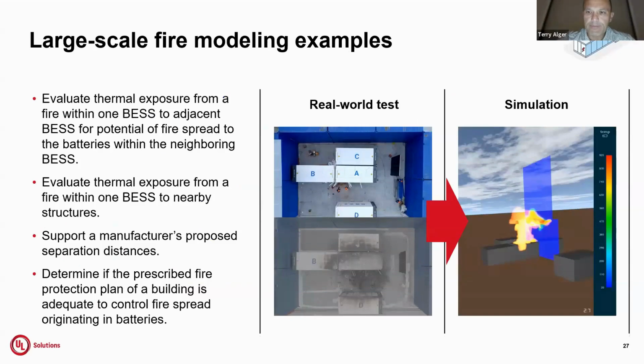Finally, there's a requirement to evaluate the thermal exposure from a fire within one BESS to adjacent BESS. This is key because in many of the significantly dangerous accidents that have occurred with battery storage systems, it's often very difficult to stop one battery energy storage system from going into thermal runaway—that's just something that sometimes happens with batteries. What we really want to do is design the system so the fire does not propagate from one battery energy storage system to another, turning a relatively minor event into a major safety incident.